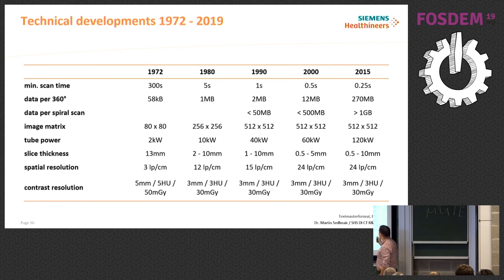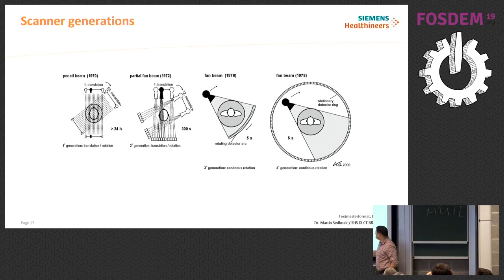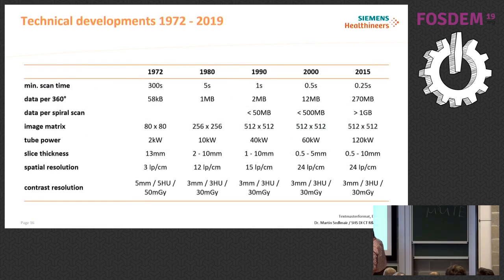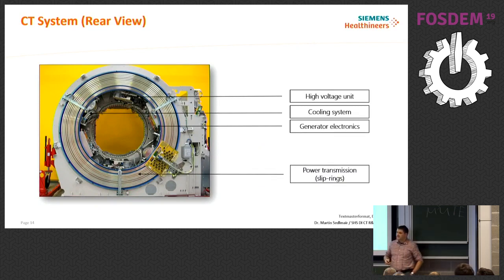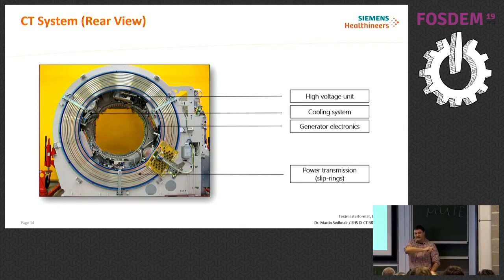The 300 seconds was reduced to 0.25 seconds primarily because the first scanners were translation-rotational systems: one X-ray source, one pencil beam, shifting then rotating. This evolved to a cone beam system where you rotate without needing to translate. The remaining problem was cables — after one rotation you had to go back. That's where the slip ring comes in: brushes connected to a metal bearing allow you to rotate forever with continuous power transmission. This also enabled the spiral scan so you can continuously scan over the patient.